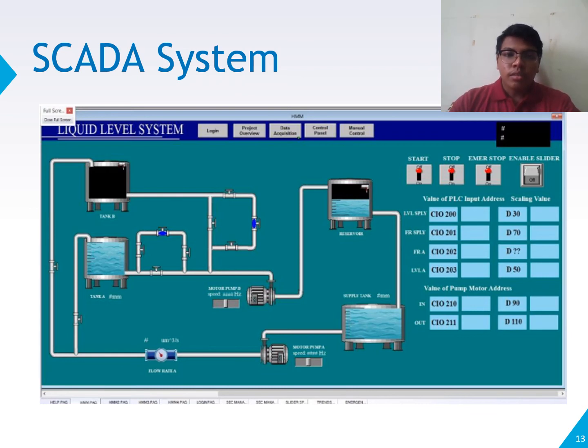Data acquisition starts at the stage of the RTU or PLC, where meter readings and status reports of the equipment are included. Both the PLC and RTU have a similar function in translating the signal from input or output devices in order to convert it to digital data and transfer it to the monitoring system to be processed. The data is then manipulated, allowing operators to track and manage the device remotely from the control room workstation. In this research, an Omron CX-Supervisor is used.